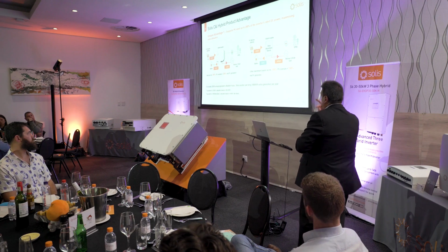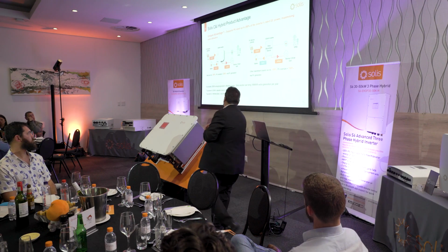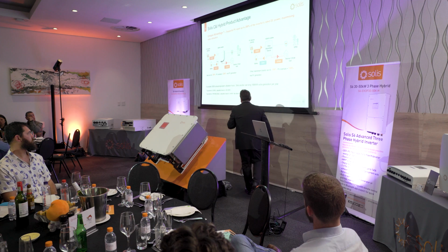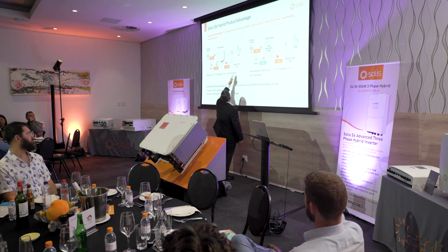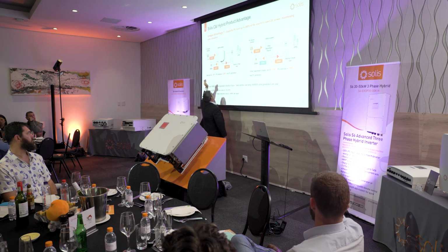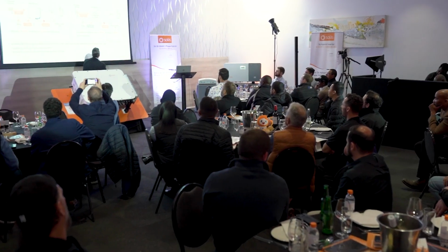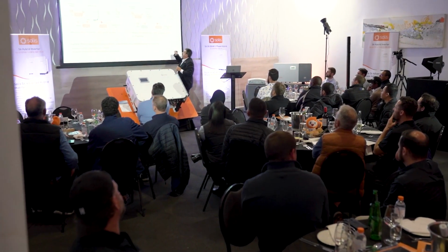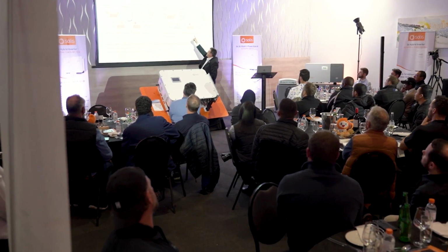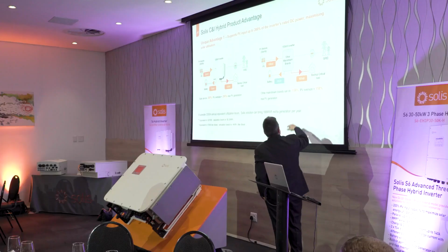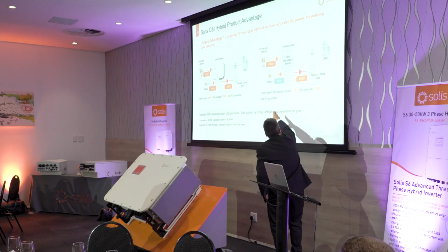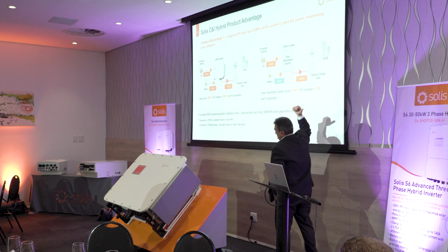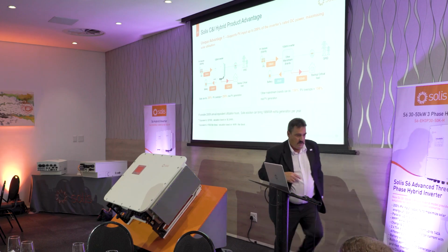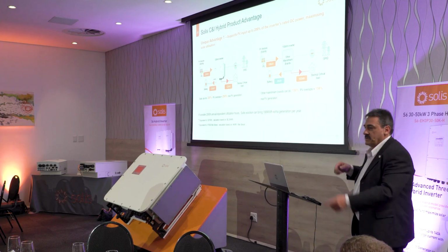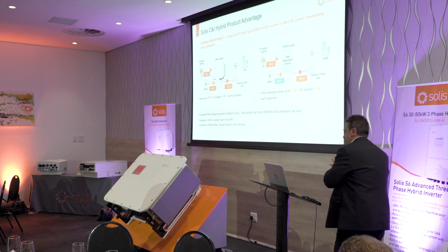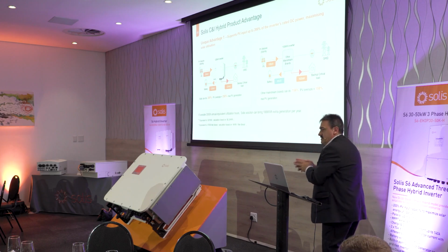So basically, with the 200% AC to DC ratio, you could get 125 kilowatt going one way, 125 going the other, and 250 coming from your PV system - or a different configuration like 156. If the batteries are full and you're not charging, you can sell the power back to the grid as well. Just remember, you cannot take 250 kilowatt out of the PV and send it all back to the grid.